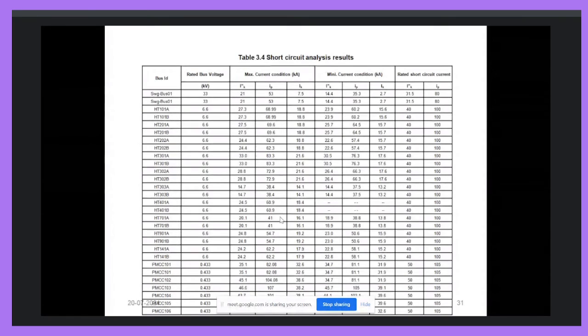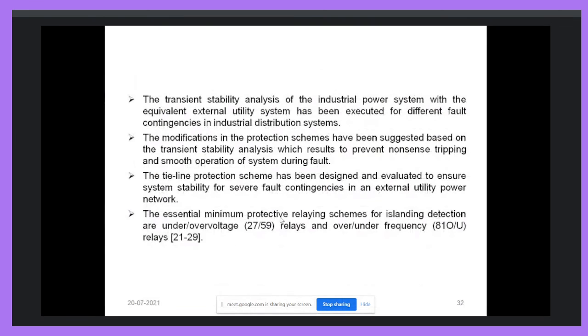To decide the rating of the network components, we require the maximum fault current which will flow through the system. The component we select must be capable of handling that maximum current. The minimum fault current value is used to set relays, because the relay must sense the minimum amount of fault current and must respond to it also. The relay should operate even at minimum fault current, and the system components must be able to bear the maximum fault current. So we have to perform the short circuit analysis to determine the minimum and maximum values of the fault current.